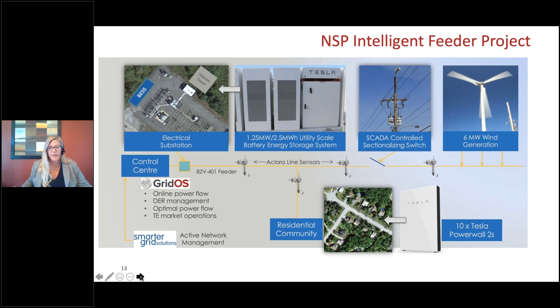We had to install a sectionalizing switch because economics dictated the size of the battery available to us, so we had to limit the size of our microgrid accordingly. At the time, we didn't have smart meters or much situational awareness on the feeder. We do have a recloser communicating at the head of the feeder, but we wanted to install line sensors across it to get baseline and operational data during microgrid operation. All of that information is brought back to our control center, where our distribution system operators use Grid OS to action the microgrid in response to the grid system.